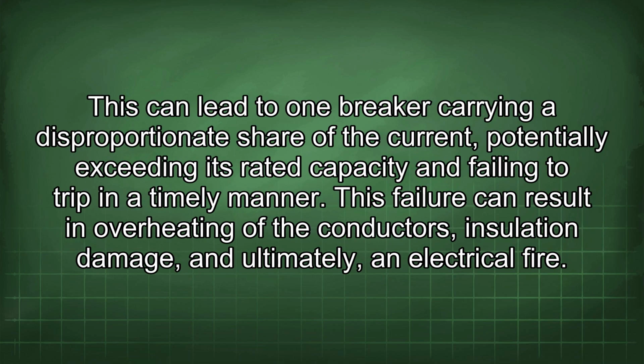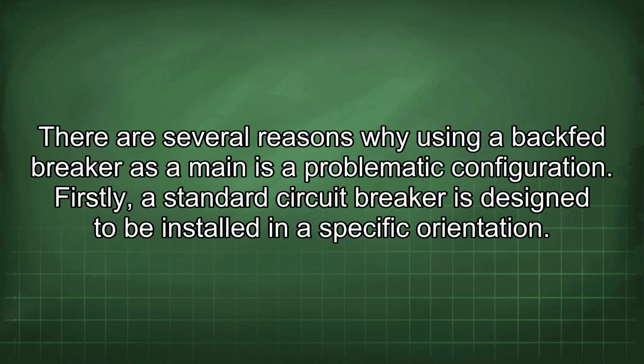This can lead to one breaker carrying a disproportionate share of the current, potentially exceeding its rated capacity and failing to trip in a timely manner. This failure can result in overheating of the conductors, insulation damage, and ultimately, an electrical fire. There are several reasons why using a backfed breaker as a main is a problematic configuration.